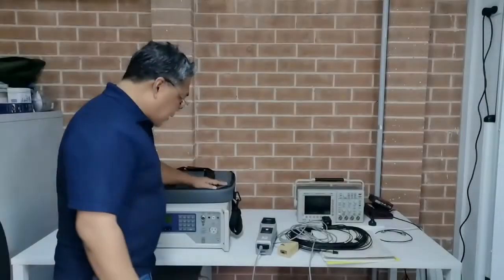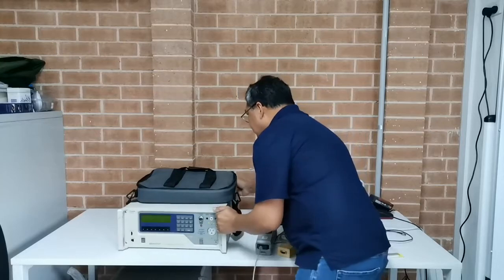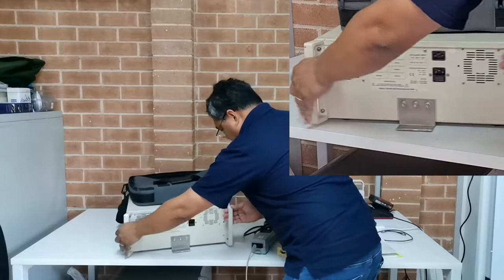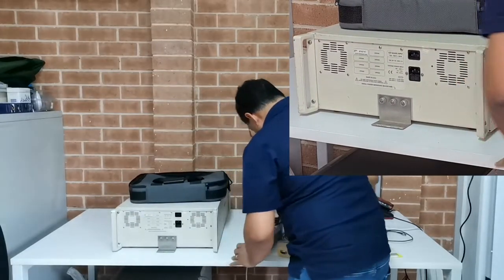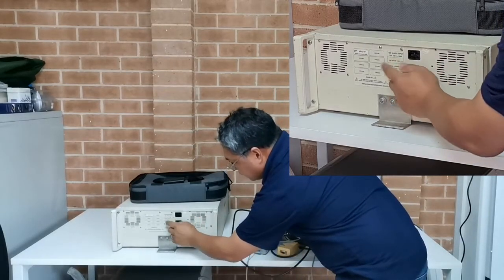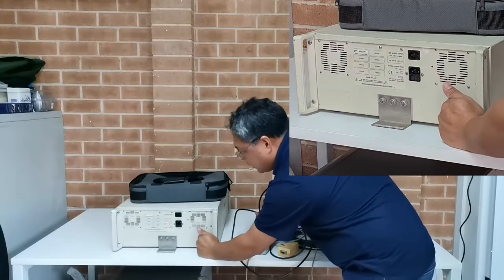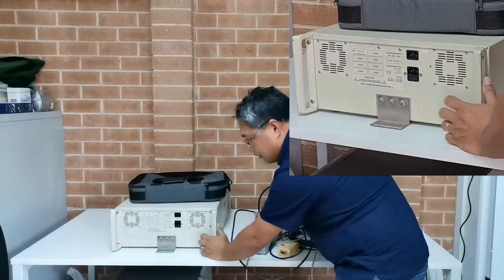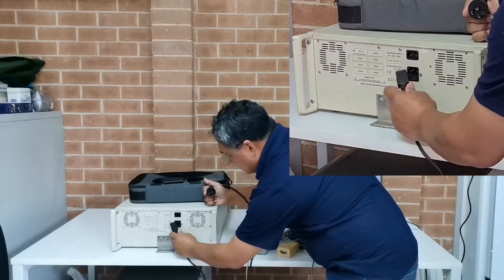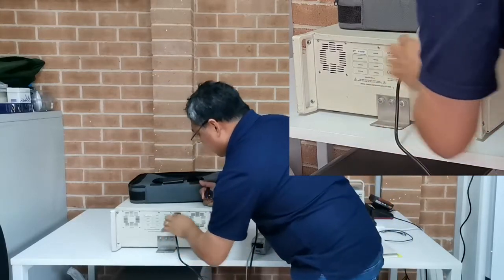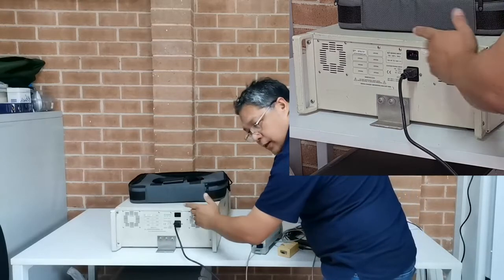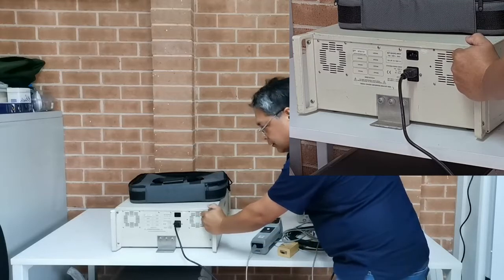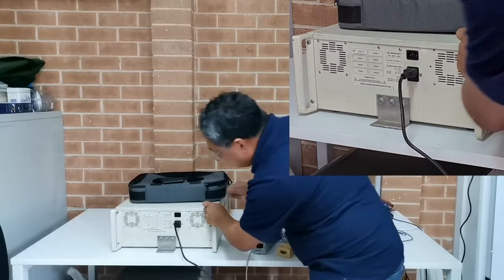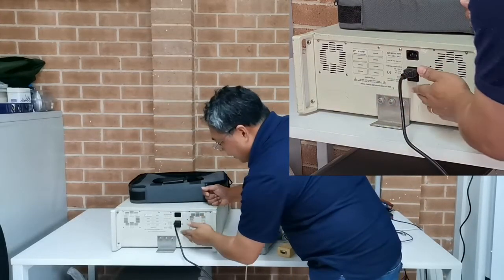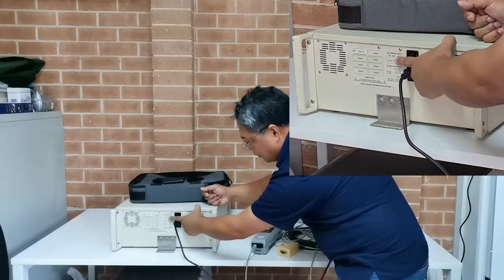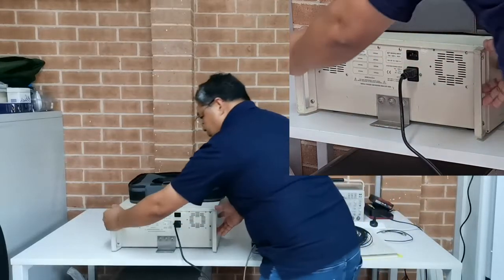So I'll be back in a few minutes. Okay, so we'll try to power up this equipment. Okay, the top one is the EUT mains input, 10 amps, and unfortunately it's only 125 volts maximum. We are in Australia, so it is at least 240 volts, but that's not a problem. So the best I can do with that, this is the system power, is only to use the external surge output, and I might build an external CDN in order to test the EUT. So I have to make sure that I won't make mistakes on plugging this one into the EUT mains input, because that says only 125 volts maximum, you see. So let's have a look.